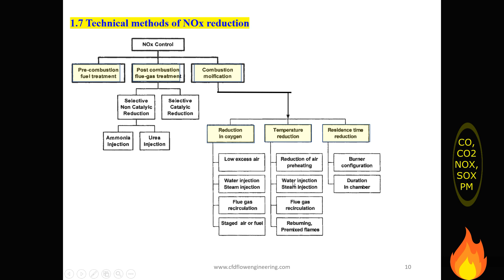The next is residence time reduction. Some burner configurations change the duration in the chamber, and that is also used. Some people try different techniques, but mostly used are the reduction in oxygen and temperature reduction, and these are the popular techniques. For combustion modification, there can be low excess air, and staged combustion is also achieved. For low NOx, low NOx burners are designed with staged air and staged fuel. Instead of supplying a single air and fuel inlet, we can use multiple inlets for the air and fuel.